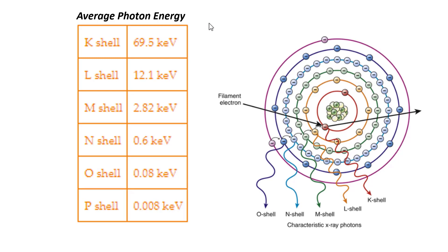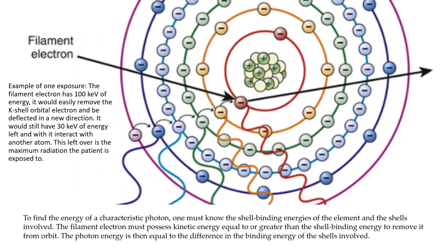The energy utilized in replacing the displaced electron is characteristic energy of that shell. Looking at the k shell, the average energy of the electrons is 69.5 keV. Where if we look at an outer shell like the p shell, the average energy of the electrons is 0.008 keV. To create exposures, we need to select an amount of radiation in milliamps, a kVp which is the highest photon energy that will be created, and a time that this radiation is being created. So we have mA, time, and kVp to create an exposure.